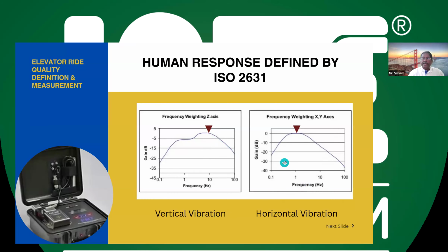Likewise, for the horizontal side, the frequency versus amplitude response curve, if you see, the major sensitivity occurs at 1 hertz. Beyond that, it keeps on reducing, drooping, and also less than 1 hertz is less. So when they formulated the standard based on ISO 2631, our body definitely cannot sense more than 100 hertz. So they formulated the guideline for the construction of the equipment so that it can capture a maximum of 100 hertz, 0 to 100 hertz only.